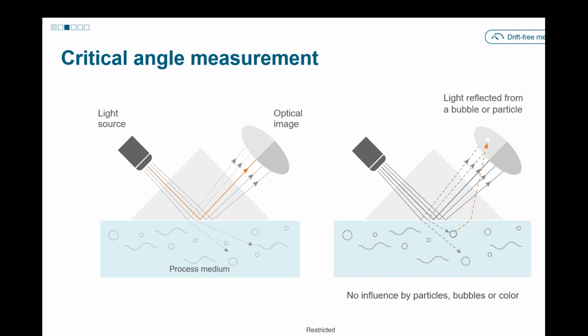All of our sensors are calibrated at the factory with NIST traceable oils that have a very specific optical property to them, and that correlates to whatever chemical scale you'll be using. So very accurate, highly accurate devices, and again, you can probably expect close to 0.1% of the concentration that you're measuring, and if that isn't what is happening in the real world, there can be things that bring it back and make it more accurate for you.